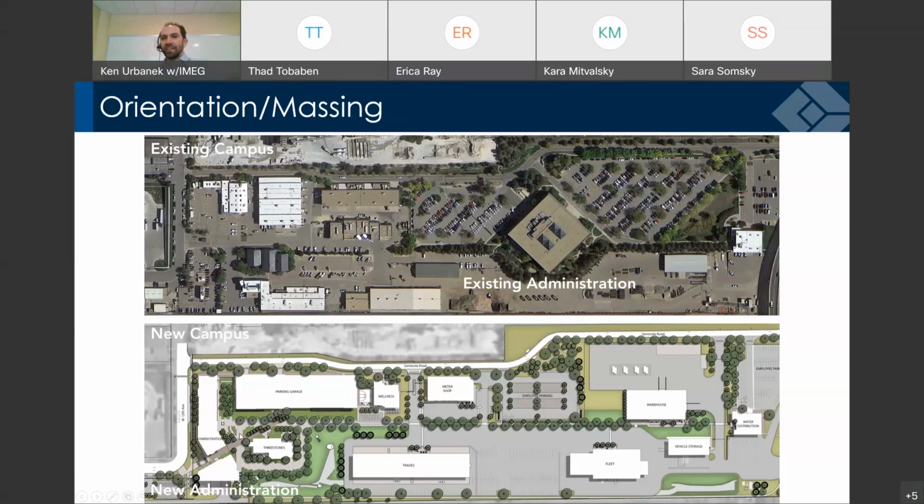And the benefit of that is that early morning sun from the east or that late afternoon sun from the west are actually really difficult to control. Because it's so low in the sky, it's pretty difficult to address that with passive solar shading. However, as that sun rises and gets to the south and is coming down from on high, that's where we can do passive solar shading, solar fins, et cetera, on the outside of the building. So that's why this east to west lengthwise orientation is actually good.